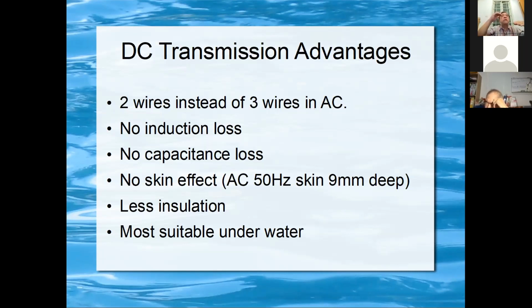So the peak is 320 volt, and the negative peak is minus 320 volt. With this peak of 320 volt, you need thicker insulation compared to 230 volt. It's like 50% higher voltage, because if your insulation is not good enough, it will puncture through and spark over. When you see sparks flying, or if the two wires are too close, the spark jumps over to the other side, the electron jumps over. That's sparking, meaning the insulation breaks down. So they need to cater to a higher voltage. For 230 volt, you times square root 2, so that's about 320. So you need more insulation.